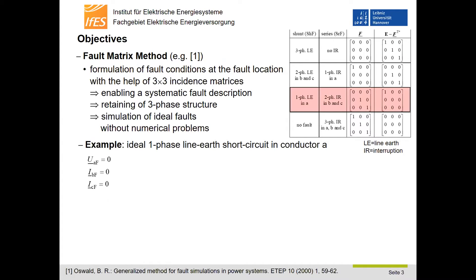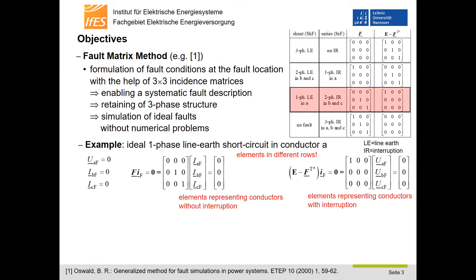For example, having an ideal one-phase line-to-earth short circuit in conductor A, the fault conditions are: voltage in conductor A is zero, and the fault currents in the faultless conductors B and C are also zero. These fault conditions for the currents and voltages can be formulated separately using a fault matrix F maintaining a three-phase structure. To carry out unbalanced fault calculations, the fault conditions have to be incorporated into the branch equations of electrical equipment and into the nodal grid equation system, respectively.